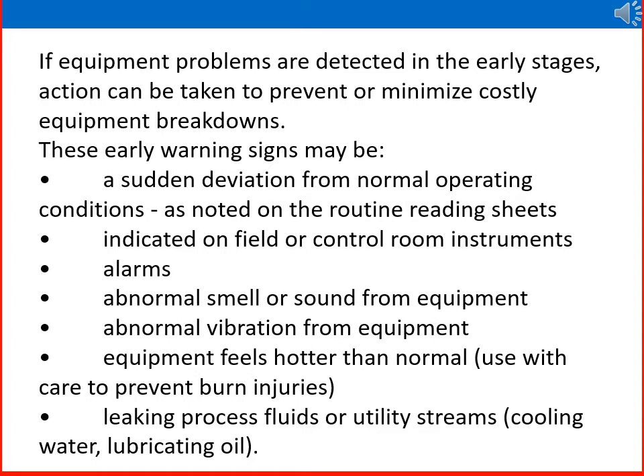If equipment problems are detected in early stages, action can be taken to prevent or minimize costly equipment breakdowns. Early warning signs may include a sudden deviation from normal operating conditions as noted on routine reading sheets, indicated by field or control room instruments, alarms, abnormal smell or sound from equipment, abnormal vibration from equipment, equipment feeling hotter than normal — use care to prevent burns and injuries — and leaking process fluid or utility streams such as cooling water or lubricating oil.